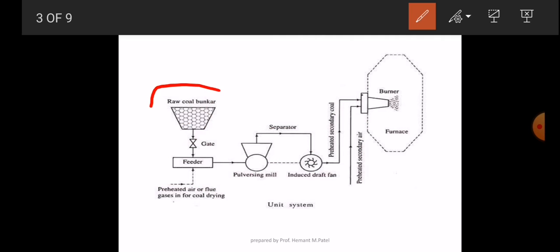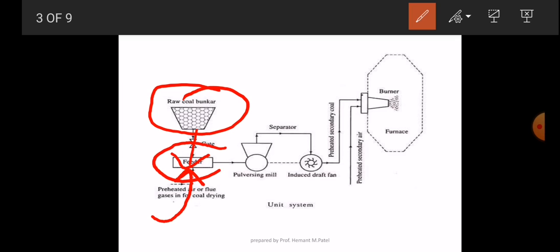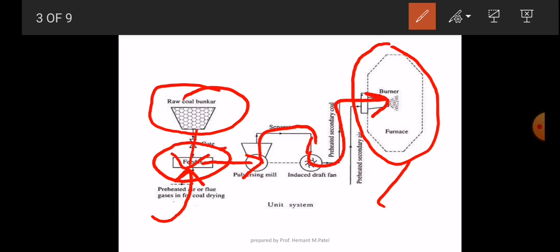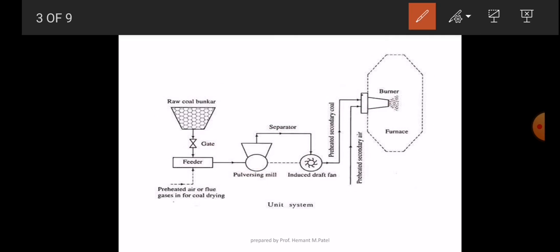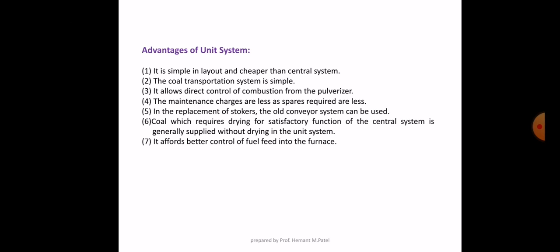This is the unit system. In the unit system, the coal goes into the feeder where preheated air is supplied for drying. Then the coal goes into the pulverizing mill where it is converted into powder coal, which passes through the induced draft fan and goes into the burner. By using pulverized coal, the efficiency of combustion and the boiler efficiency is increased compared to using coal in lump form.